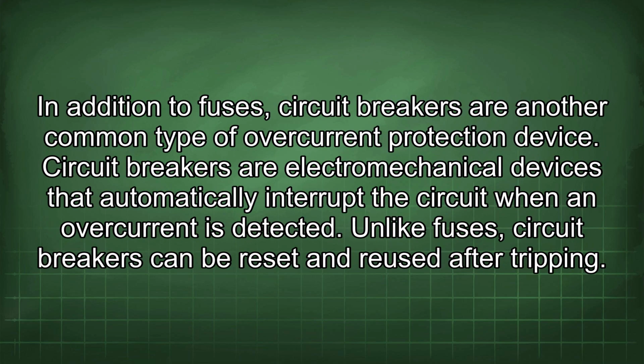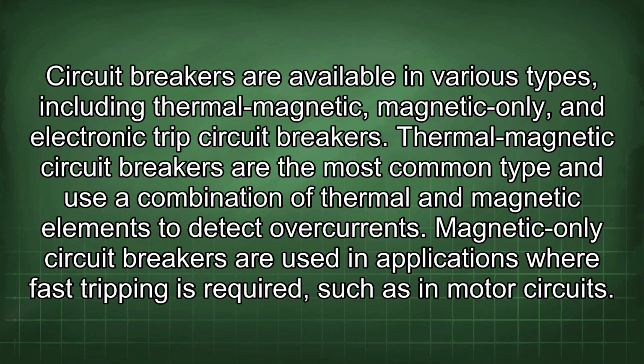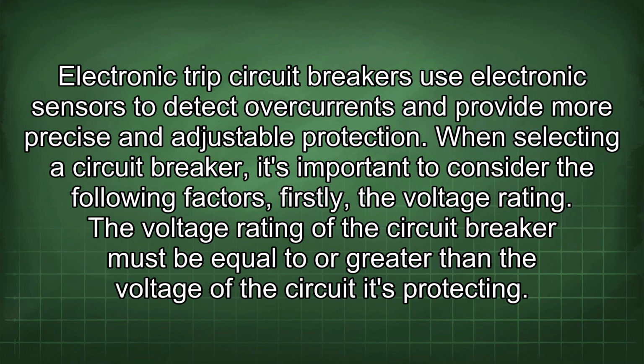In addition to fuses, circuit breakers are another common type of overcurrent protection device. Circuit breakers are electromechanical devices that automatically interrupt the circuit when an overcurrent is detected. Unlike fuses, circuit breakers can be reset and reused after tripping. Circuit breakers are available in various types, including thermal magnetic, magnetic only, and electronic trip circuit breakers. Thermal magnetic circuit breakers are the most common type and use a combination of thermal and magnetic elements to detect overcurrents. Magnetic-only circuit breakers are used in applications where fast tripping is required, such as in motor circuits. Electronic trip circuit breakers use electronic sensors to detect overcurrents and provide more precise and adjustable protection.